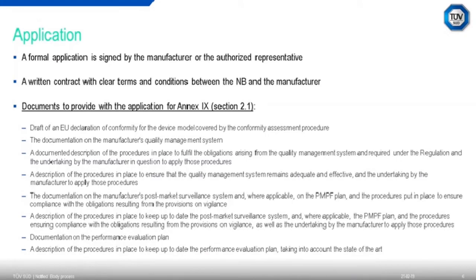There is a set of elements that you have to provide, and they are key to provide during the application as well; they are listed here. Among them, you have the draft of the EU Declaration of Conformity. You have some documentation on your quality management system, on the description of the procedures, and the description of the manufacturer's post-market surveillance, right? What you have in place, what you're planning to put in place. You have to have documentation on your performance evaluation plan. So not necessarily what you have done, but at least having the plan.